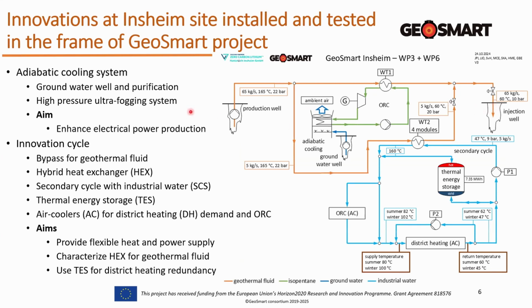The first thing was to install an adiabatic cooling system, so we improved the function of the air-cooled condenser. A groundwater well was installed along with a purification system, and we spray water below the air-cooled condenser to cool down the air locally. This is how we can increase power production during hot summer days.